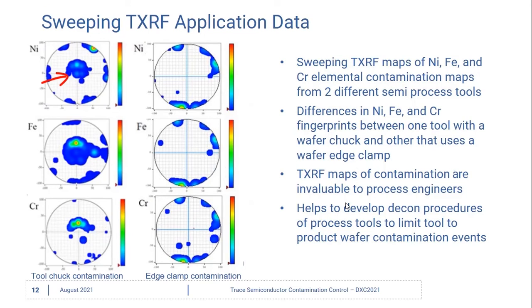On this second wafer, the nickel, iron, and chromium contamination was located mainly around the edge of the wafer. This processing tool used a wafer edge clamp made of stainless steel, and that was determined to be the source of the contamination on this wafer.